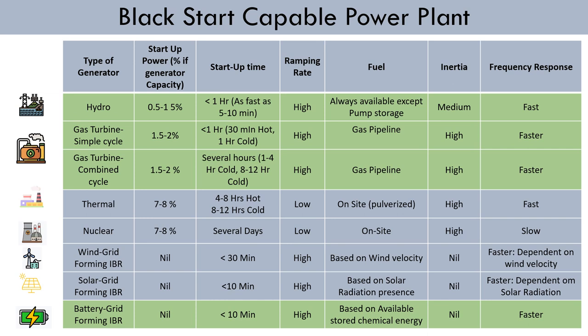This stems from the rotating mass of their turbines and generators, which aids in stabilizing the system frequency during the restoration phase. Overall, the combination of quick startup, high power output, on-site fuel supply, and frequency stabilization renders hydro power plants as highly effective Black Start capable resources. Gas power plants are considered as the second best choice for Black Start capable resources due to several key factors. One of their strengths is their quick startup time, allowing gas power plants to initiate electricity generation relatively swiftly during the grid restoration process.